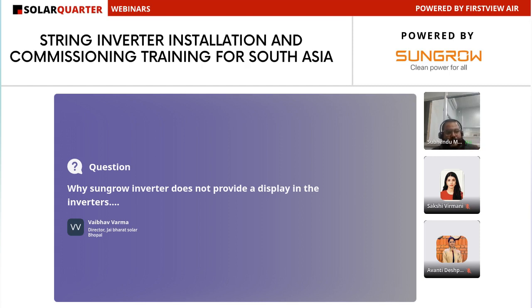We could not check the inverter status otherwise. We had to check from the display, but nowadays we can connect from our phone. A phone is accessible to every person. We have inbuilt Bluetooth on it, and by connecting with Bluetooth, we can check. A display may be damaged shortly, since most inverters are installed outdoors, so the display will be damaged in a short time. But LED does not get damaged in a short time. LED has a long life, so we are using LED.